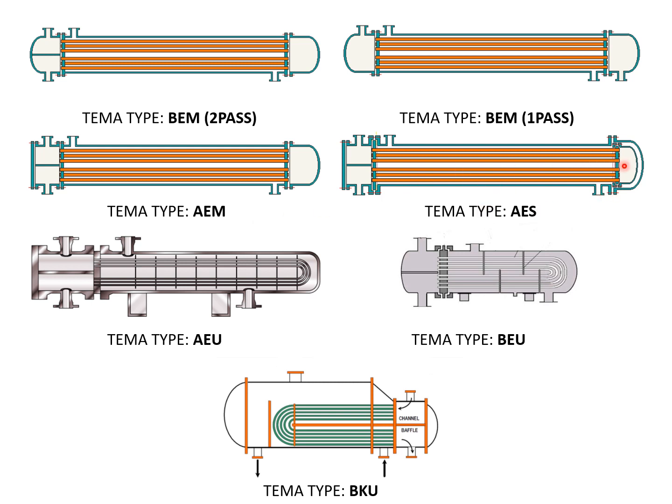So what is AES? In AES, you have a moving type of tubes. We use this, for example, when you have a medium in a tube which is at a very high temperature, and that will have very high thermal expansion. In that case, we use the moving type, where we have some mechanical arrangement.